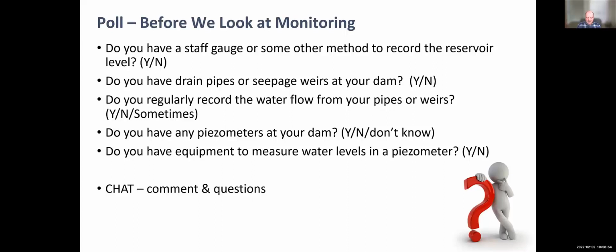Do you have piezometers? I expected a high percentage not to have them, but it's only 53% of people who do not have them. There are some people that aren't too sure whether they have them or not. For those that are not too sure, it's probably worthwhile exploring that some more. Sometimes we have piezometers, they're there at a dam, but they're not functioning anymore.